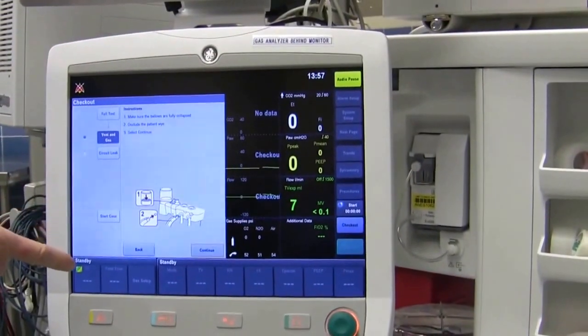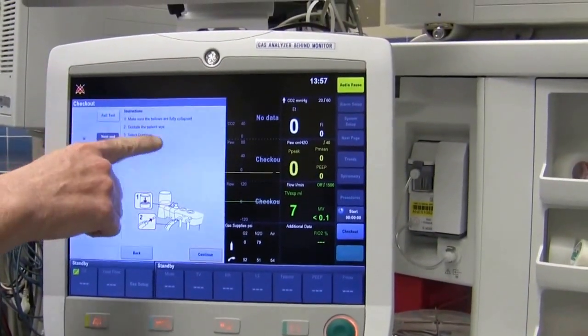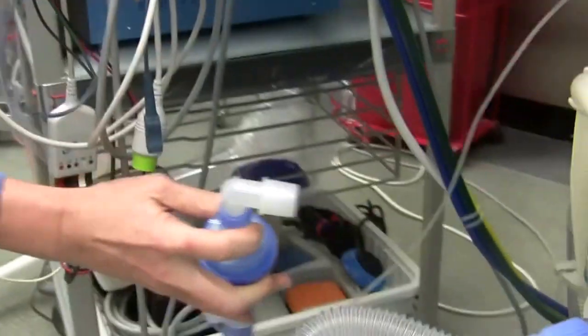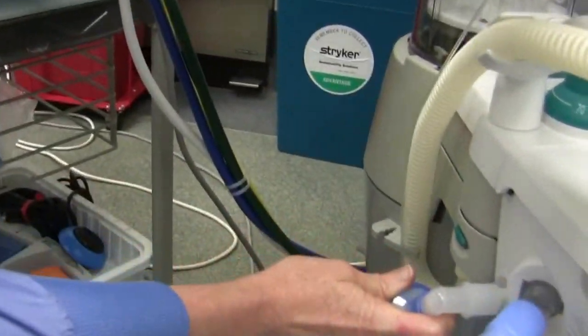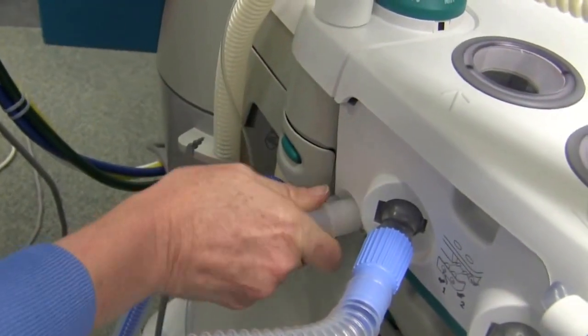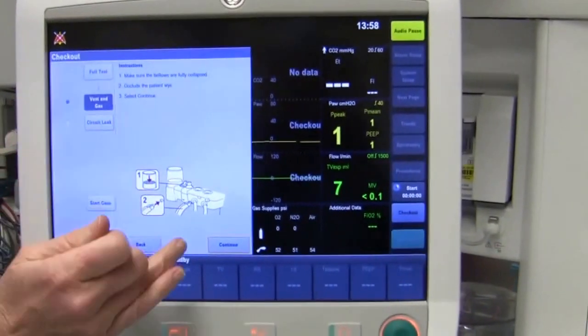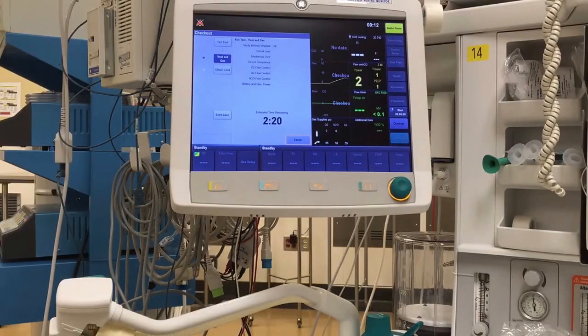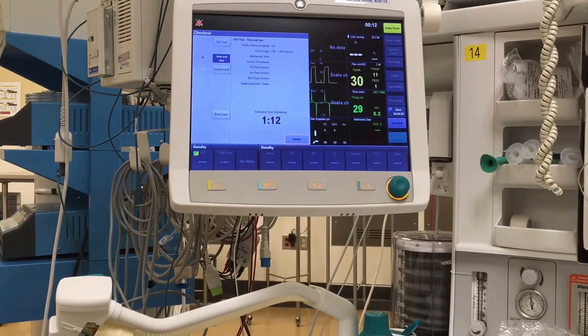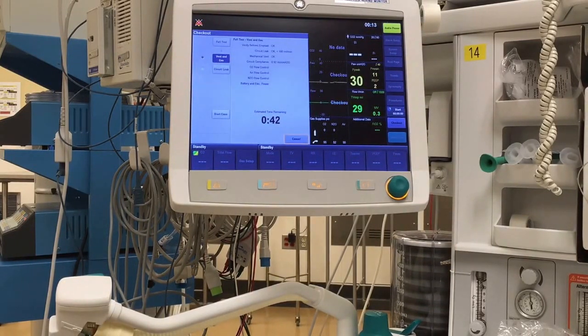The second part to the test is that it says make sure the bellows are fully empty, which they are. This time they want you to occlude the patient Y, and the occlusion knob is right here. Connect it there and select continue. This part takes about 2.5 minutes. This is when you will do other things like draw up your medicines, etc.